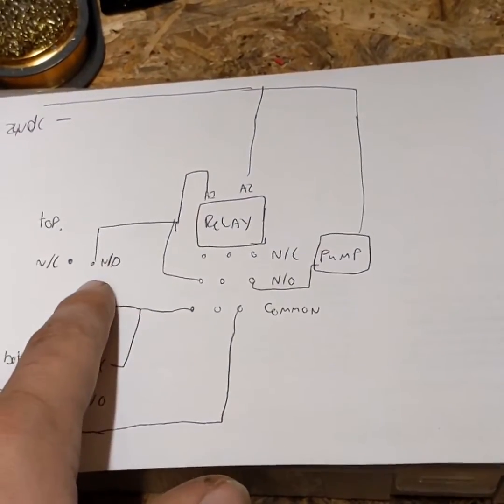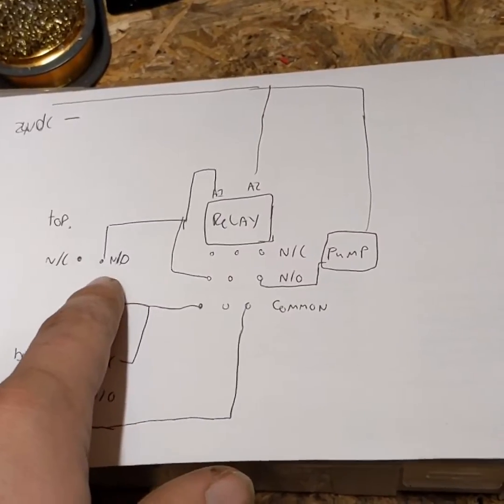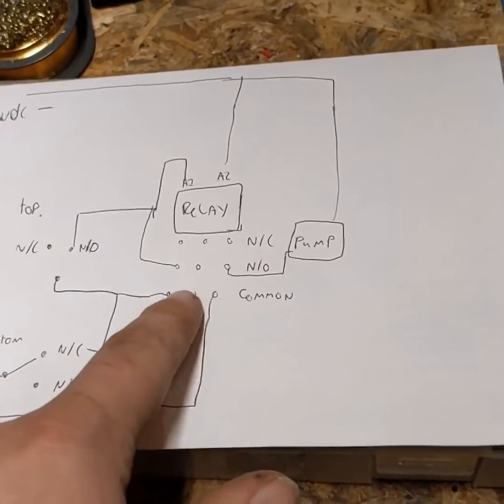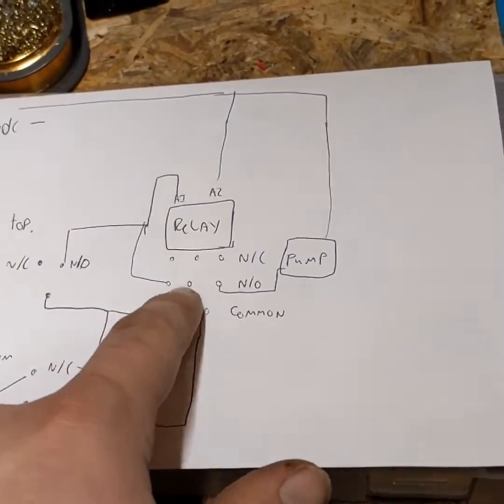So this is just a momentary switch. As the tank goes down, the switch will then close, but it's powered through this normally open contact on the relay to keep the relay energized.